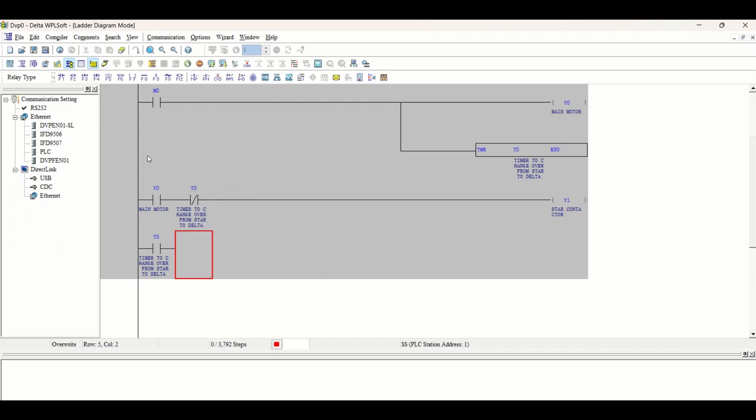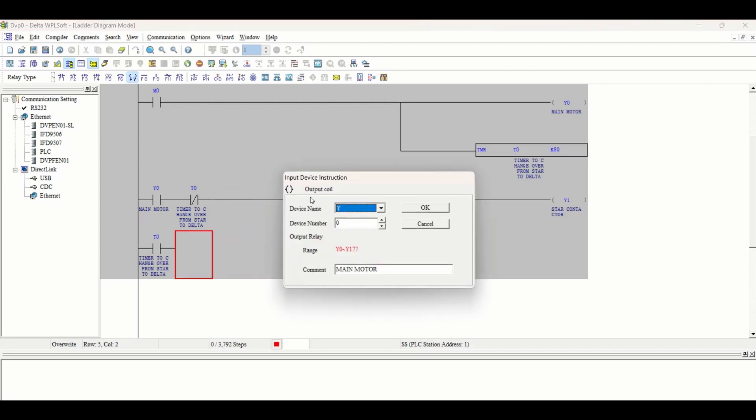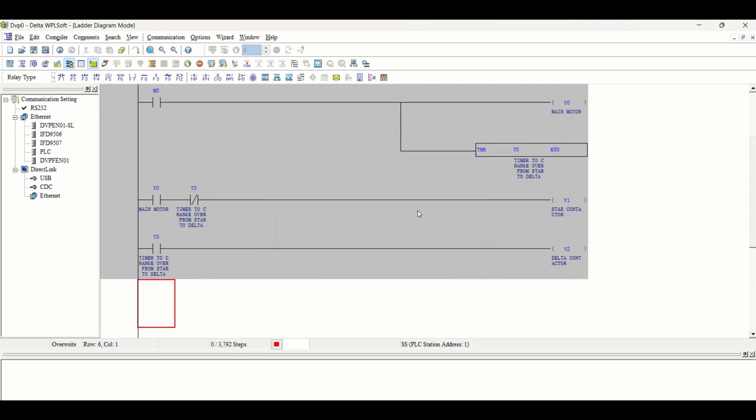T0 will stop the star contactor and in parallel it will start our delta contactor Y2. This will stop and this will start, and the main motor will continue. Now the main motor will be switched to delta after 8 seconds.